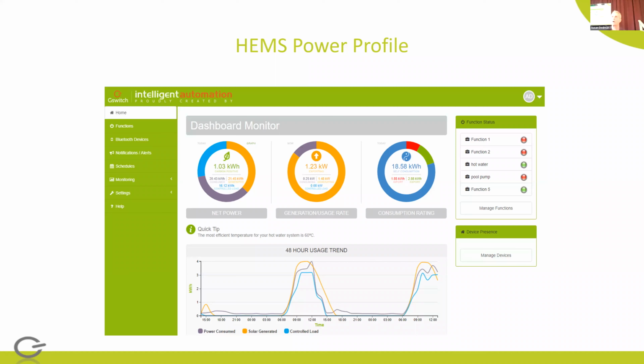The 5 megawatt limit: one of the main costs of setting up a microgrid is the grid connection process you go through with Essential Energy. When you go over connecting more than 5 megawatts of generation, that price skyrockets - it's already hundreds of thousands even below 5 megawatts. And that 5 megawatt is solar plus the battery plus the diesel generator, so anything happening all at the same time. That does limit the size of what you're operating.